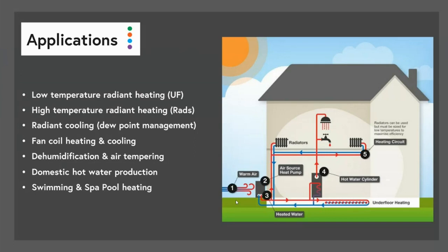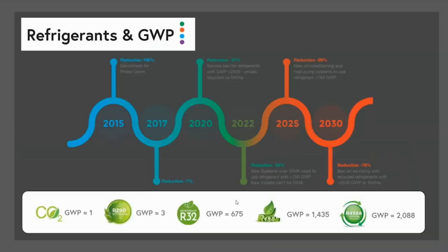They can do domestic hot water production, and the beauty of R290, like we talked about before, is that it produces very high temperatures, which means we can do very fast recovery on hot water cylinders using that technology. And then it can also do swimming and spa pool heating, all part of the same system. So move on a little bit more.